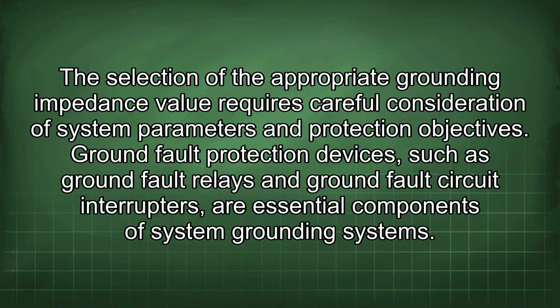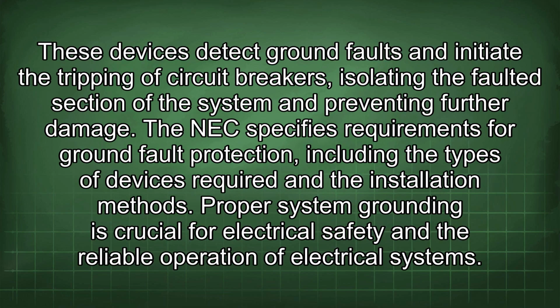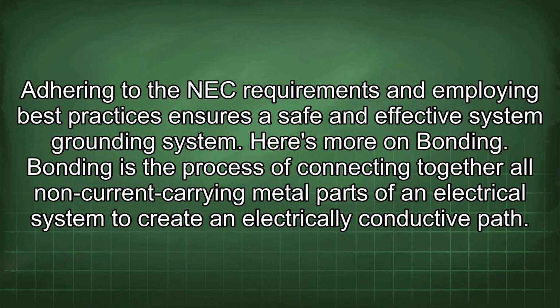Ground fault protection devices, such as ground fault relays and ground fault circuit interrupters, are essential components of system grounding systems. These devices detect ground faults and initiate the tripping of circuit breakers, isolating the faulted section of the system and preventing further damage. The NEC specifies requirements for ground fault protection, including the types of devices required and the installation methods. Proper system grounding is crucial for electrical safety and the reliable operation of electrical systems. Adhering to the NEC requirements and employing best practices ensures a safe and effective system grounding system.